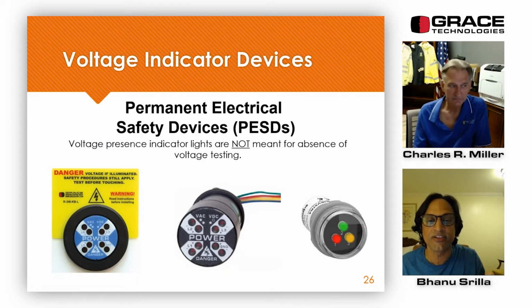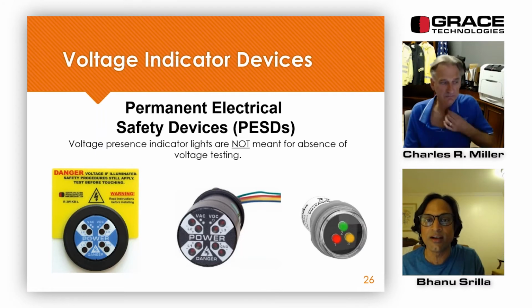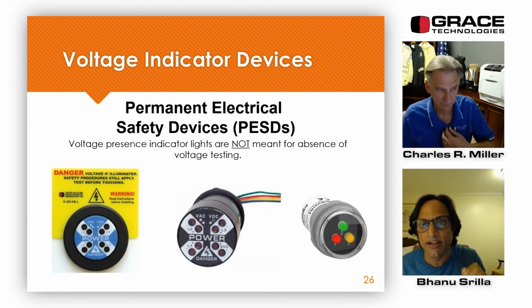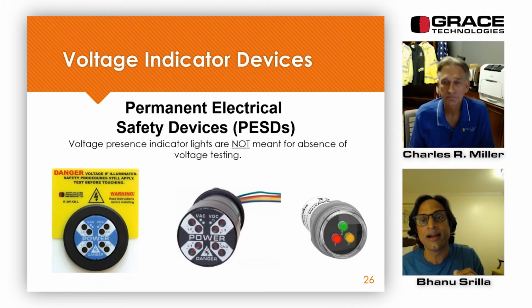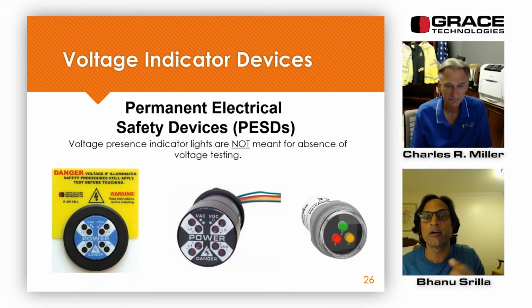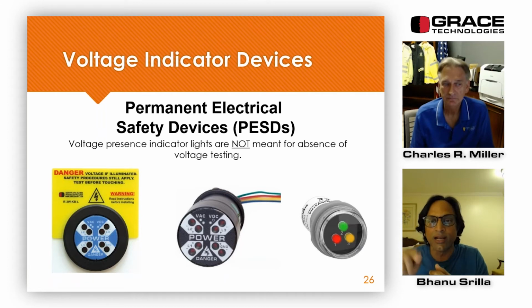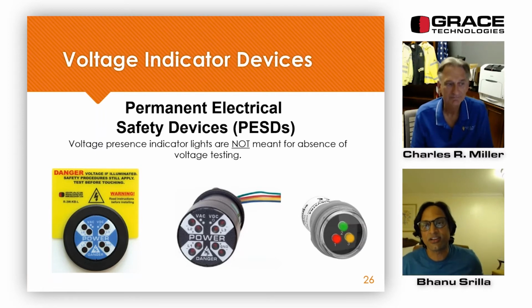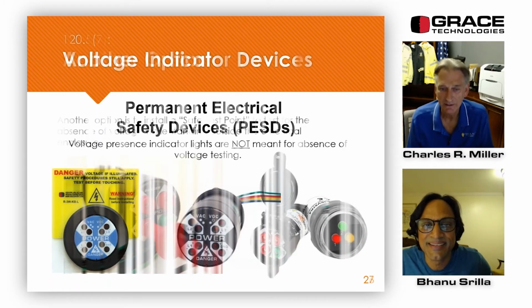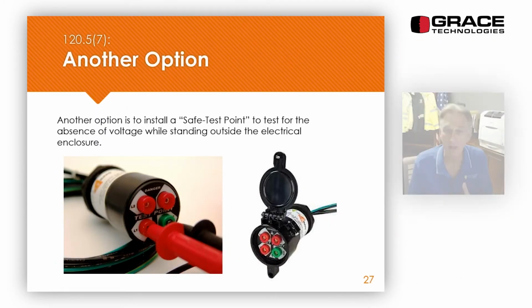There's a lot of confusion around the industry that these devices are for visual voltage presence verification only. This can be used by task qualified persons like your mechanical operator, or the one who is performing the secondary side of the equipment maintenance, meaning someone who is turning the disconnect off and doing a bump test and verifying or working on the secondary side of a pump, not touching the electrical circuit parts or components. Thanks, Charlie.